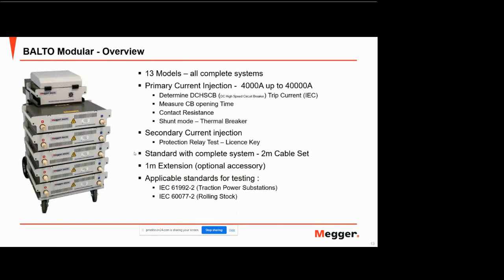So Balto comes in two forms. There's a Balto modular. So the modular, we have 13 models, all complete systems. So you buy a complete system, fully operational. The main difference between all of the models is the amount of current that you require in order to test your DC high-speed circuit breakers. So it's modular in design. You can choose to go from 4,000 amps all the way up to 40,000 amps, depending on what your requirements are. Okay, but every Balto modular performs a number of standard tests.